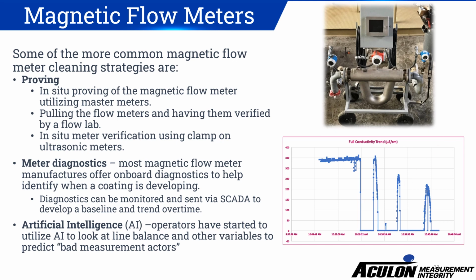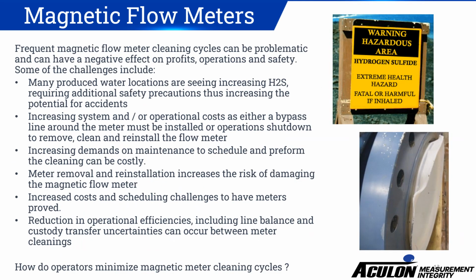Artificial intelligence: some operators have started to utilize AI to look at line balance and other variables to predict bad actors, in other words, which meters need to be looked at, and use this information to prioritize and schedule their flow meter maintenance. Frequent magnetic flow meter cleaning cycles can be problematic and can have a negative effect on profits, operations, and safety. Some of the challenges include increasing H2S, requiring additional safety precautions, which can result in an increased potential for accidents. Increasing system or operational costs, as either a bypass line around the meter must be installed, or the meter must be shut in so it can be removed, cleaned, and reinstalled.